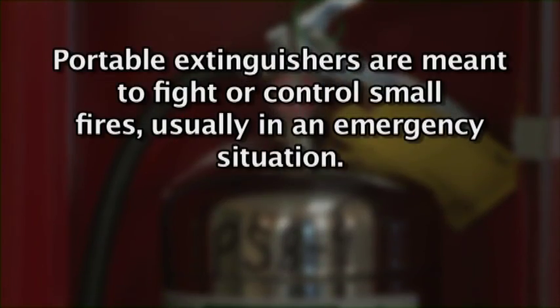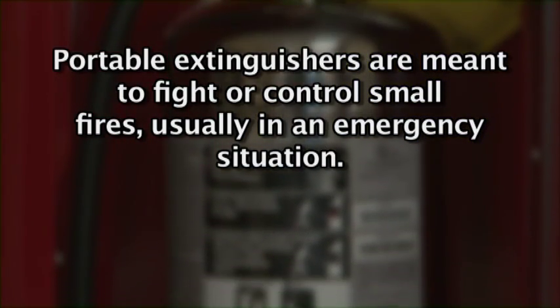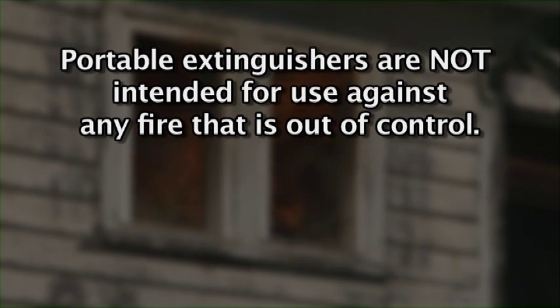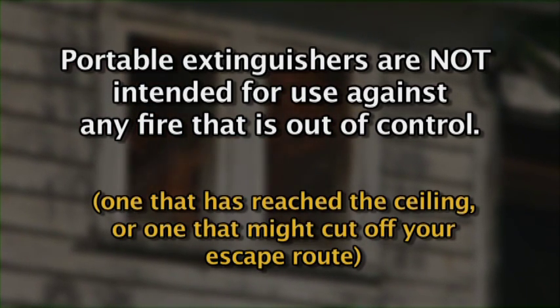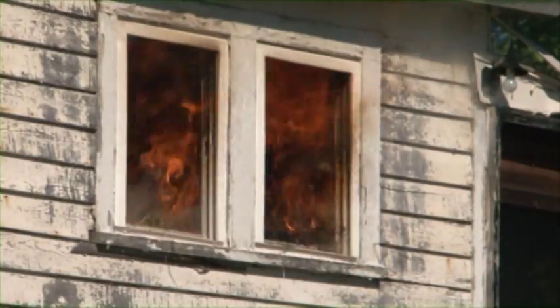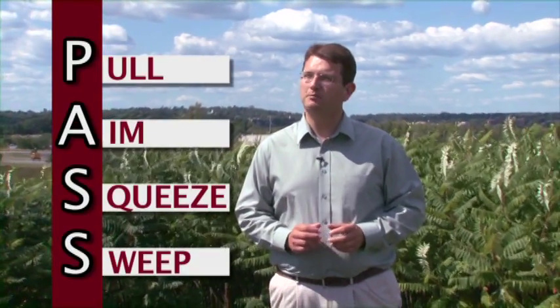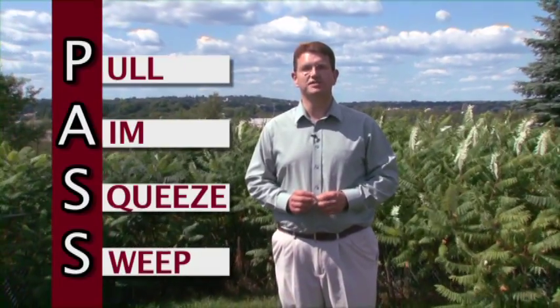The last thing is the use of the fire extinguisher. Know what the tool is used for. Portable extinguishers are meant to fight or control small fires, often in emergency situations. It is not intended for use on any out-of-control fire, such as one that has reached the ceiling or one that endangers the user by cutting off one's escape routes. And of course, to use one, remember the simple acronym PASS. Pull, aim, squeeze, and sweep.